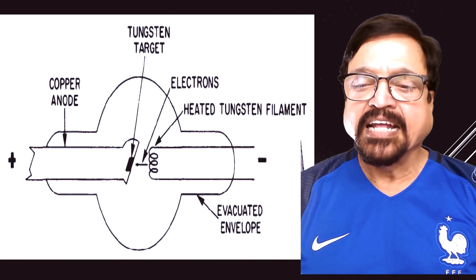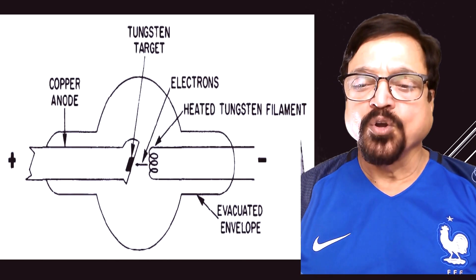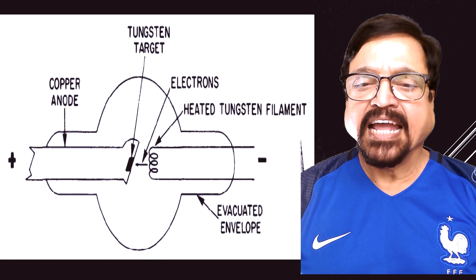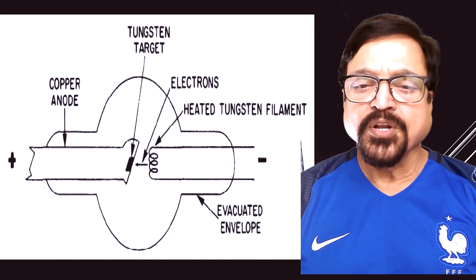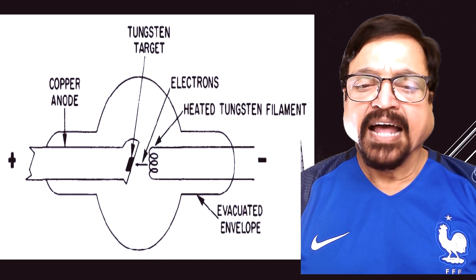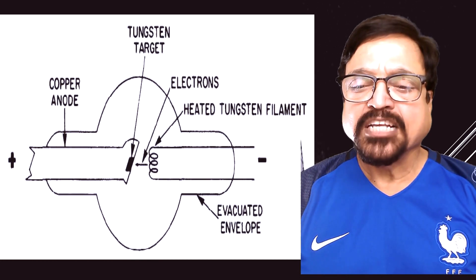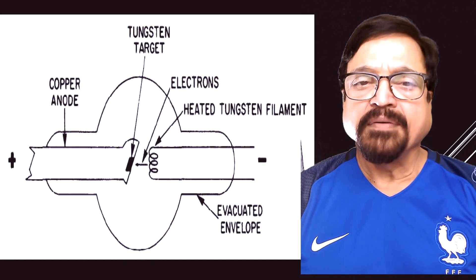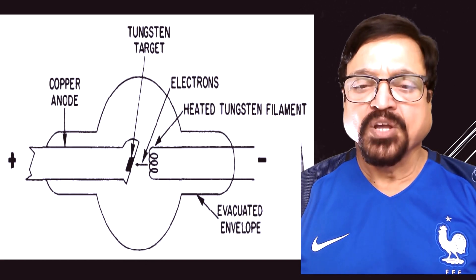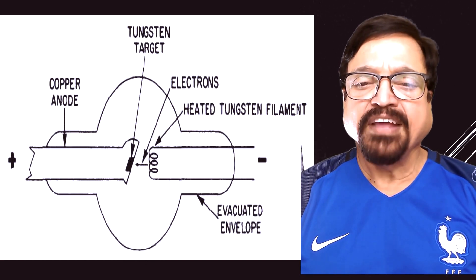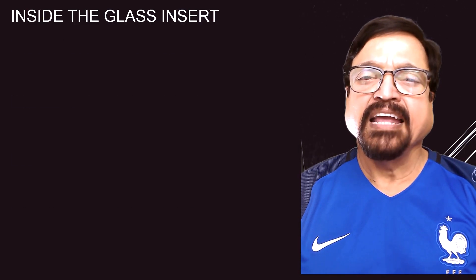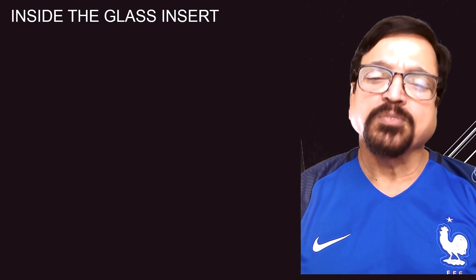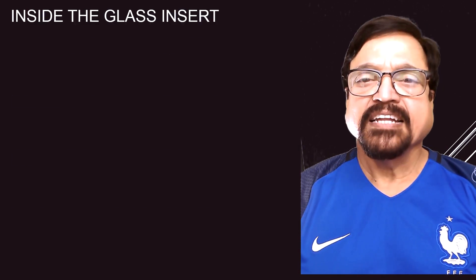This is the stationary anode tube. You can see the anode is small, consisting of copper on the outside and a small focal spot of tungsten. There are no moving parts here. We have a fixed anode which is of copper, and in that the focal track or focal spot is made of tungsten.